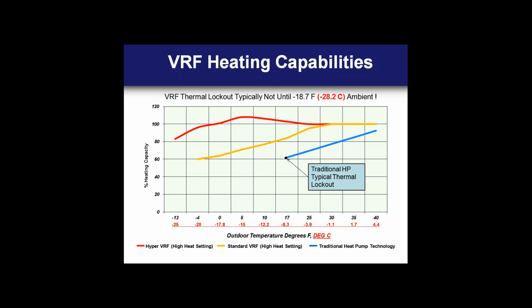C. And then if you move into what's called flash injection scroll technology, which a lot of VRF manufacturers have, that allows you to achieve actual guaranteed test data down to minus 25 C with heating capacity up above 80% in a lot of cases. And the other thing important to note is this is not a thermal lockout condition where these graphs end for VRF. That is strictly just the end of their rating conditions, they'll continue to operate typically down to -28°C.